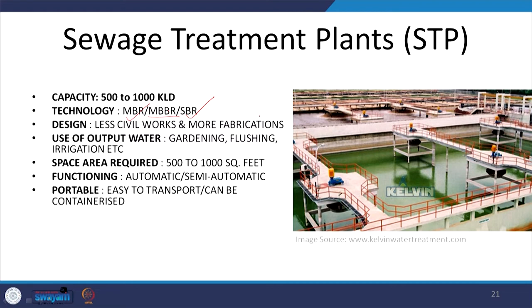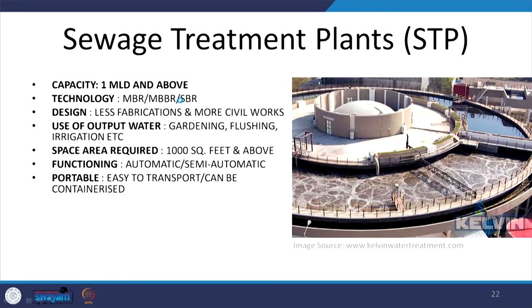At further increased capacities, MBR, SBR, and MBBR are common types of STP that can be scaled up in size and volume. These require less fabrication but more civil work, and the water can again be used for gardening, flushing, and irrigation, but they require relatively more area. Space requirement gradually increases as volumes increase, and transportation and portability become gradually more difficult as capacity grows. For very high capacities, any of these technologies can be used.